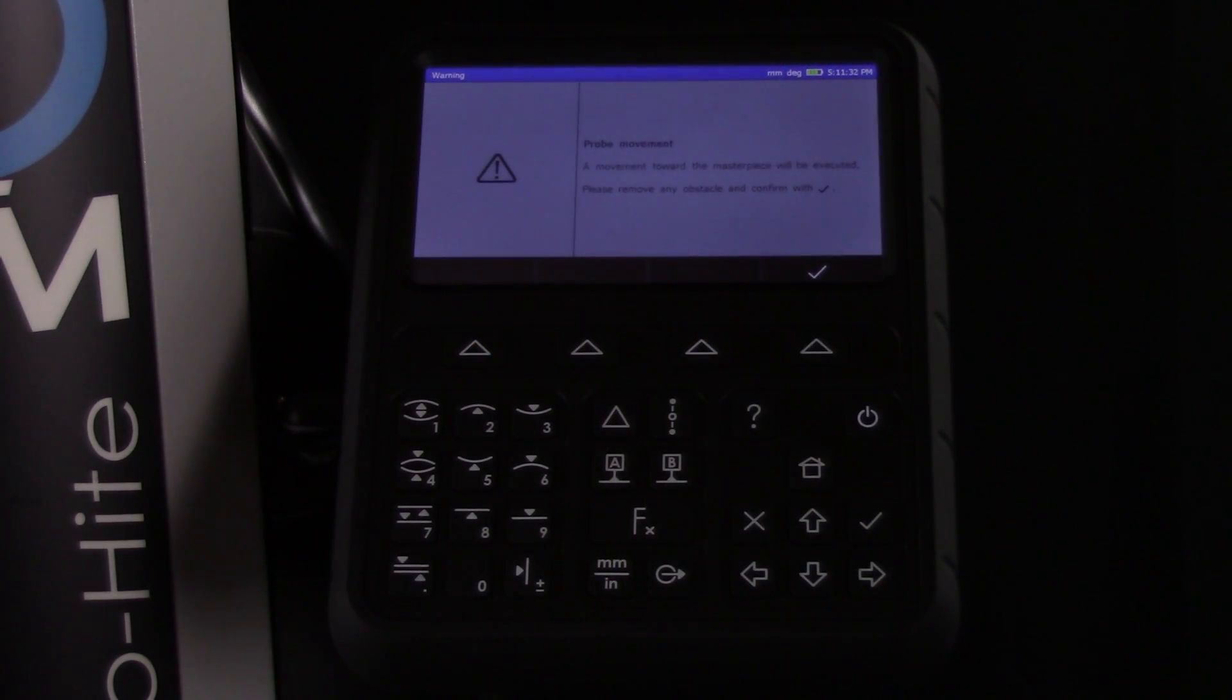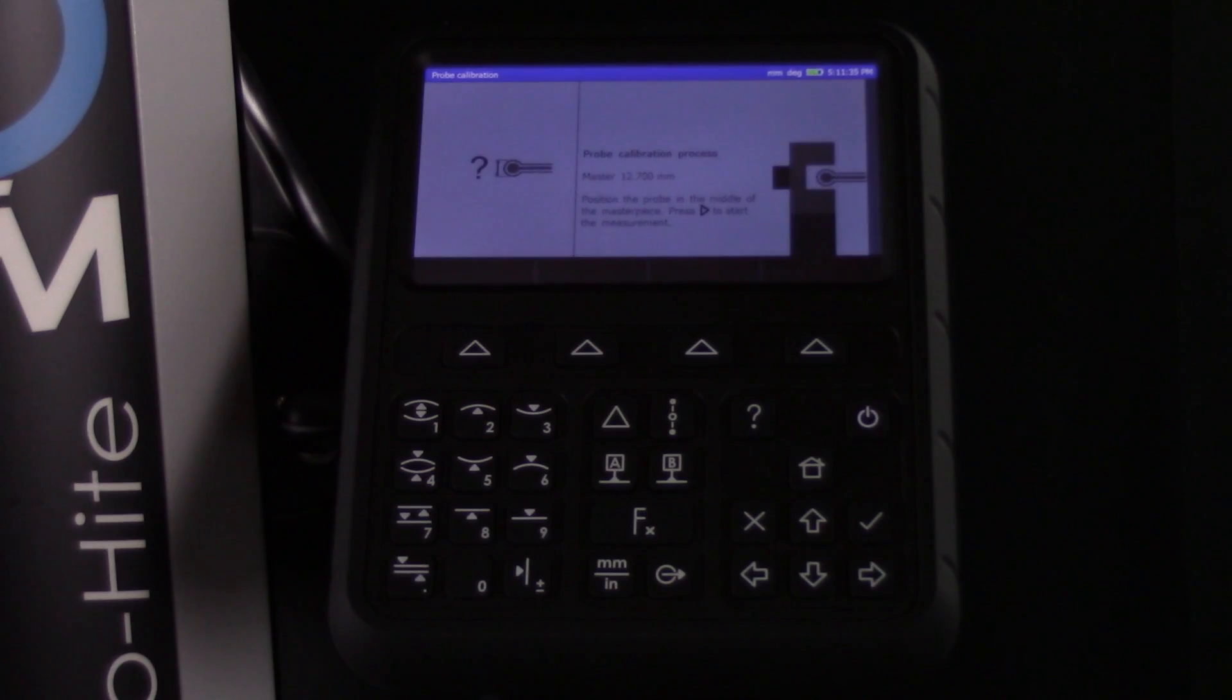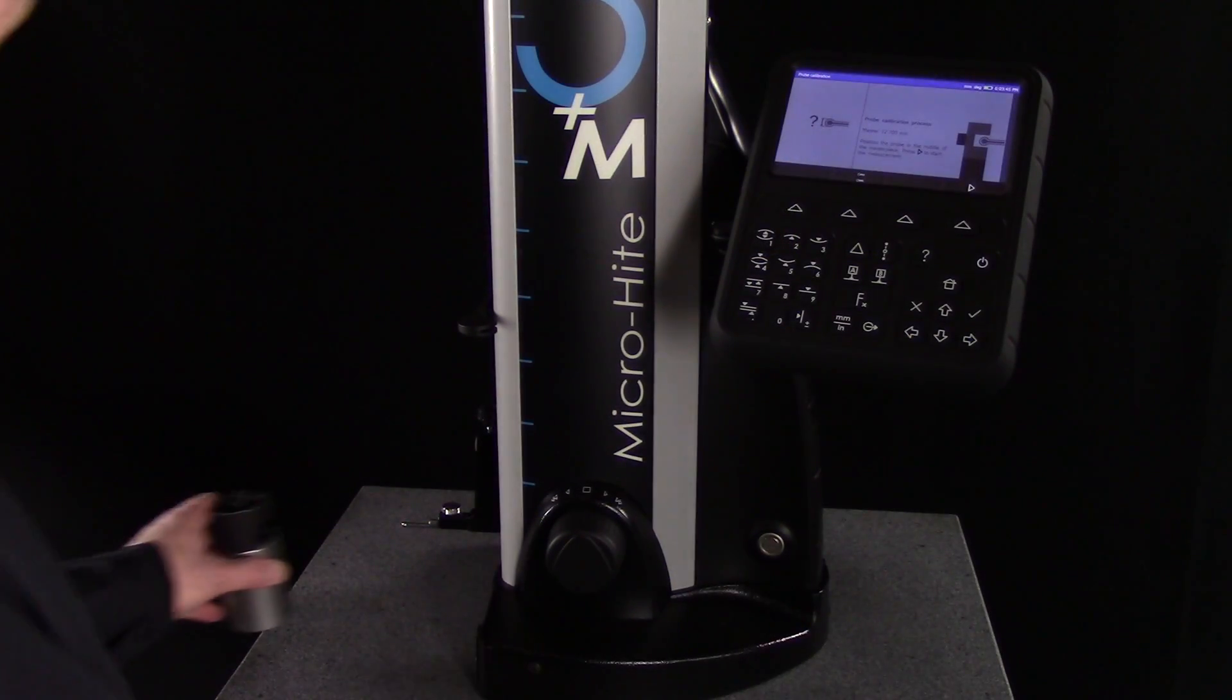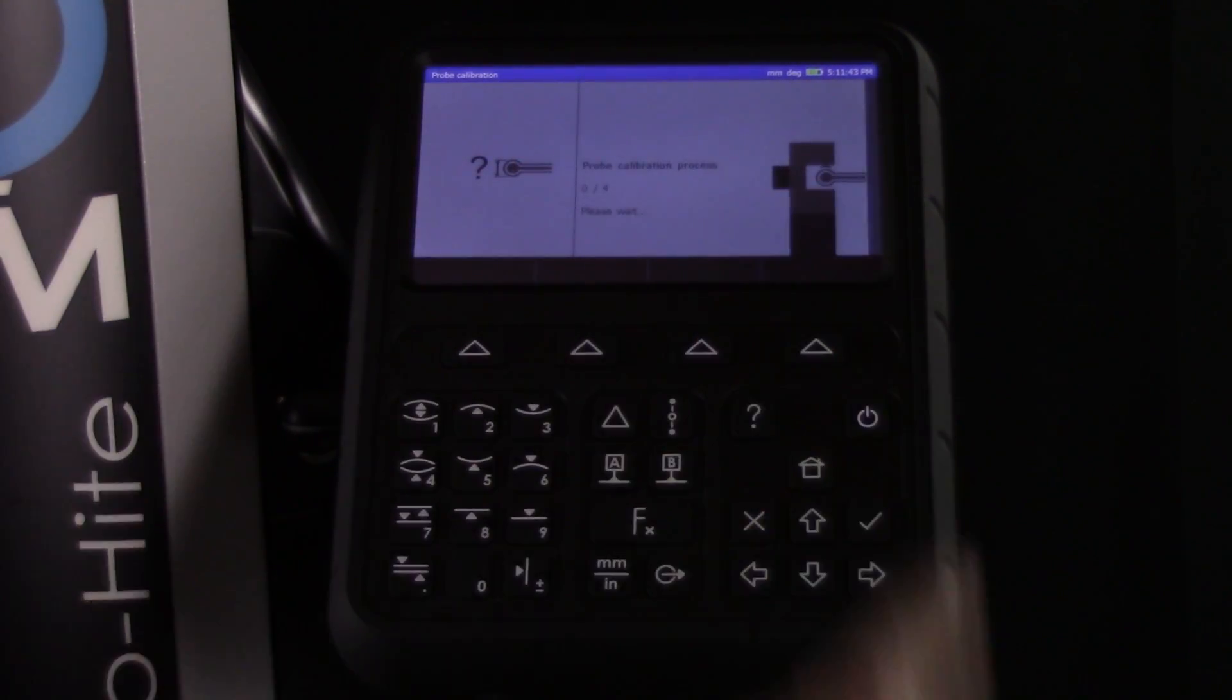Next, the display will indicate that it's time to calibrate the probe using the Masterpiece. Move all other parts away from the probe and position the Masterpiece for calibration. Then press the right arrow button on the display to begin the calibration sequence.